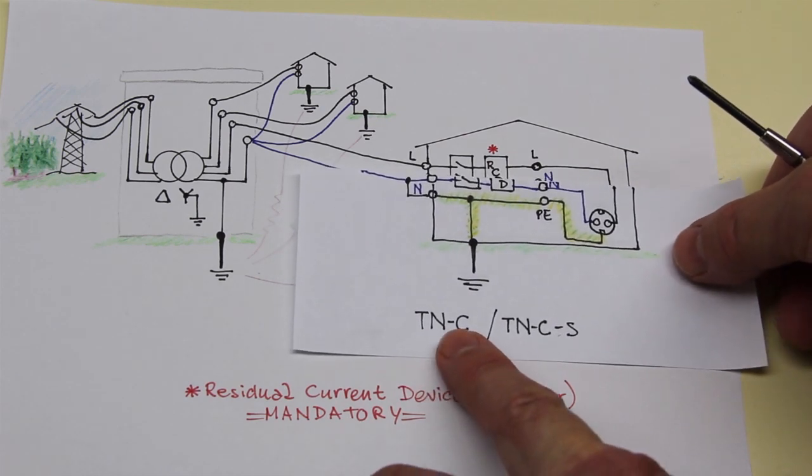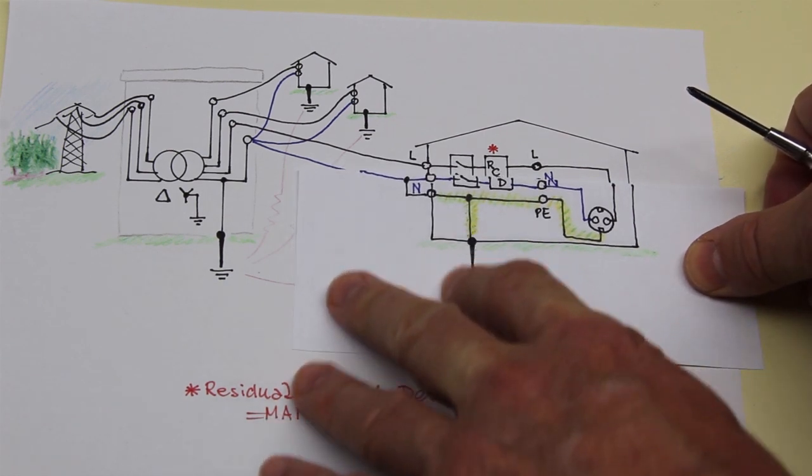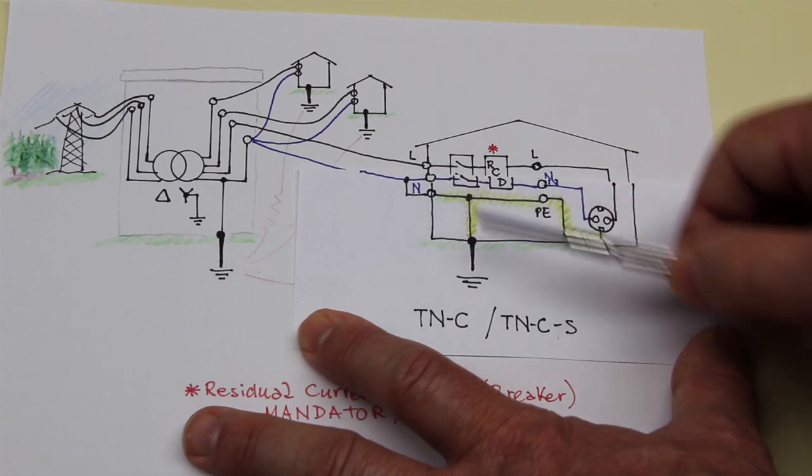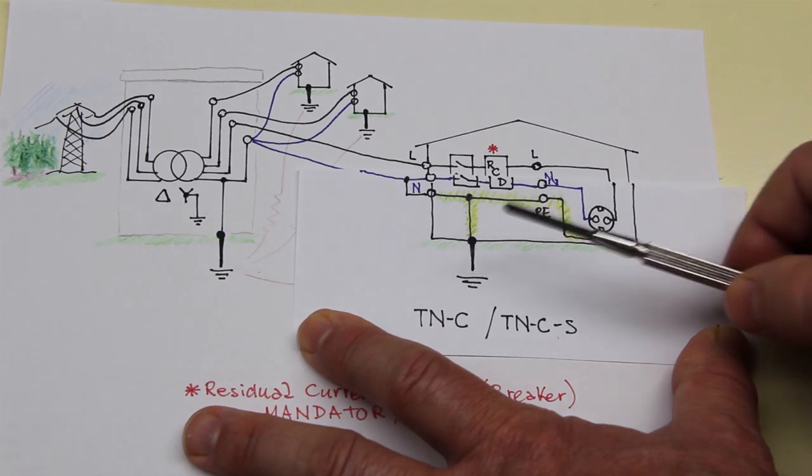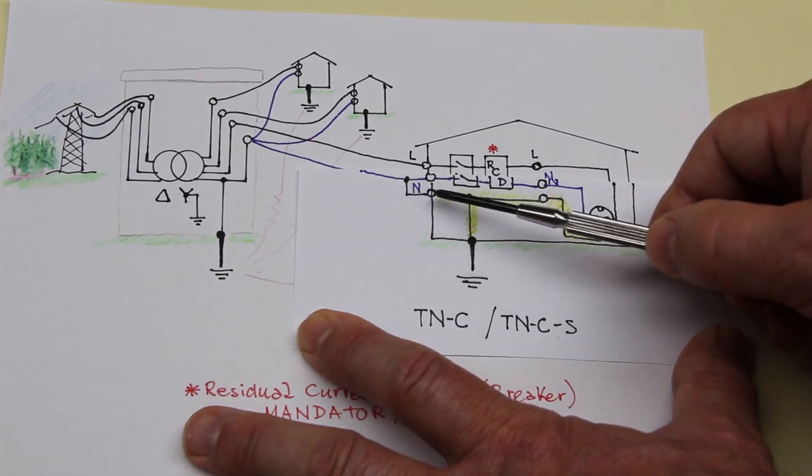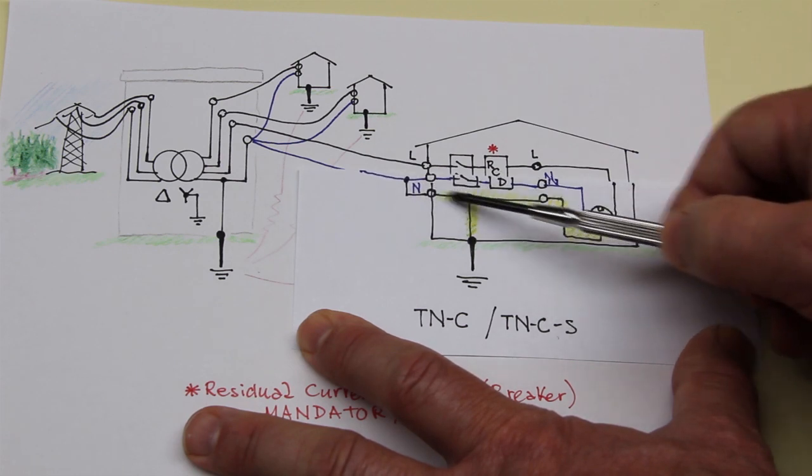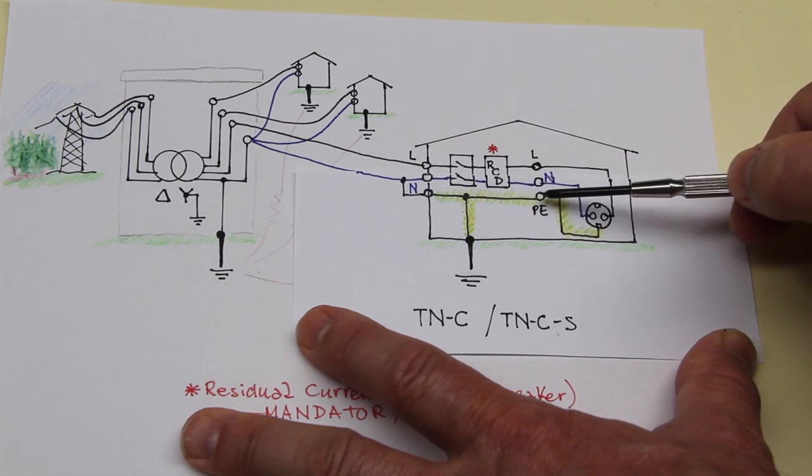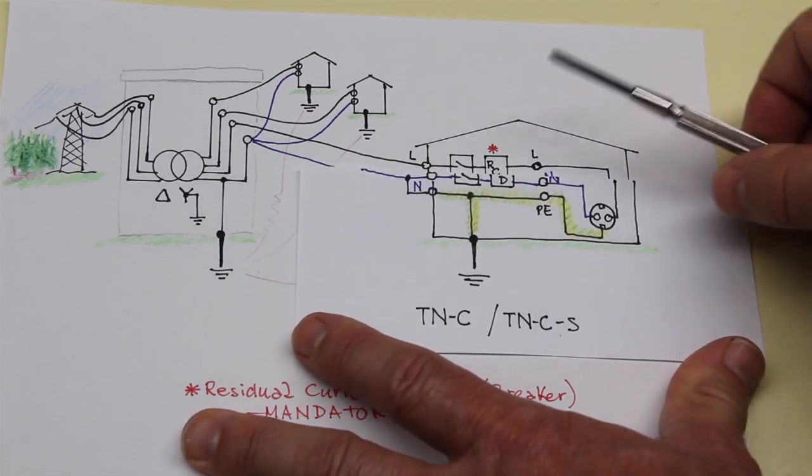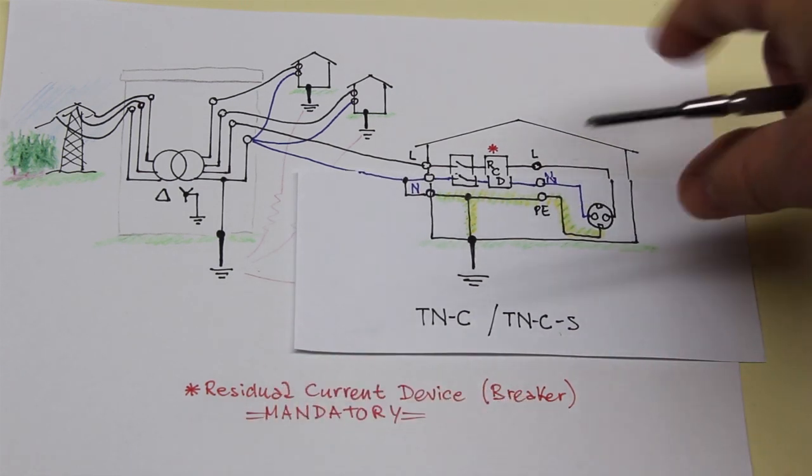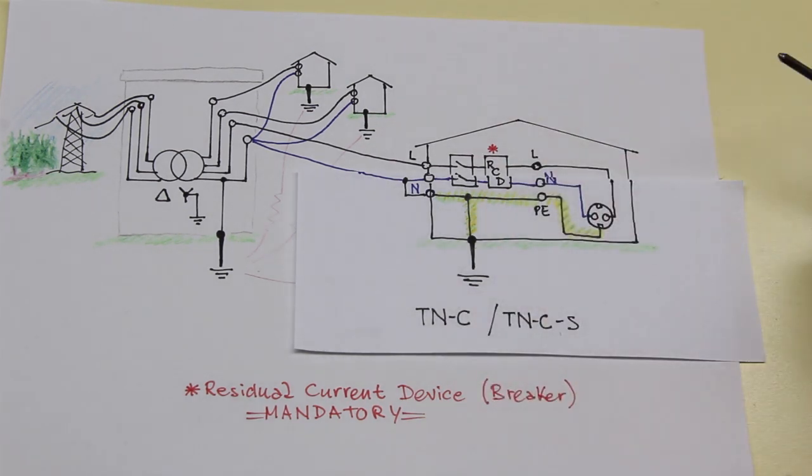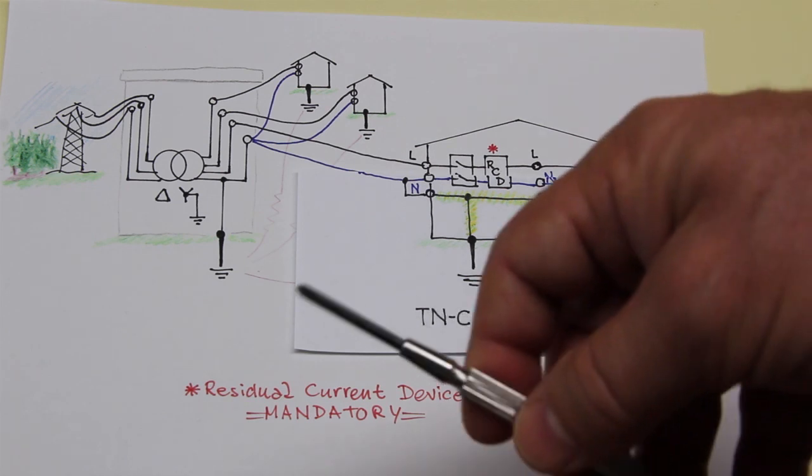In certain locations of Europe, however, there's another possible arrangement that is named TNC or TNCS, but more likely TNC. The difference is where this joint is located, and in this case the neutral is linked to the protective earth. In this case the neutral is at the same voltage of the protective earth. In North America there are sometimes this kind of arrangement or other kinds of arrangements, and in other places of the world there are other earthing systems.